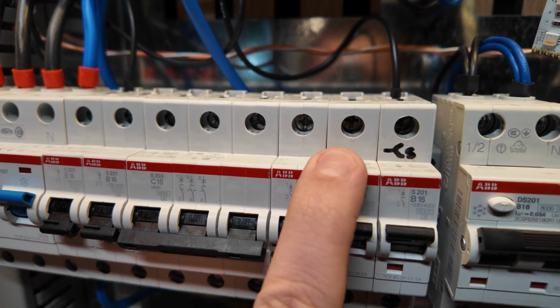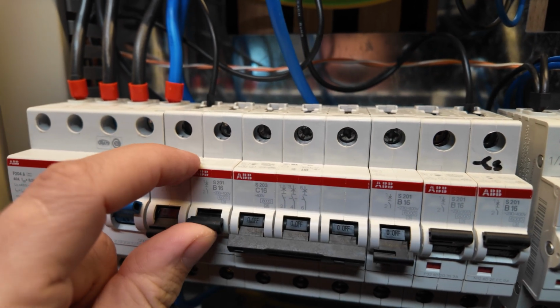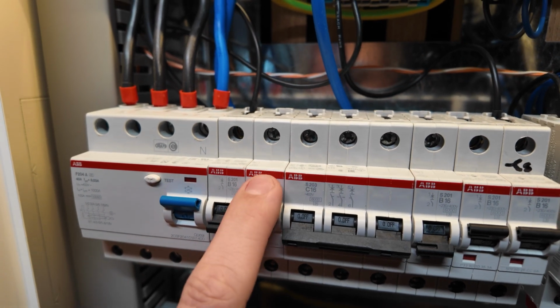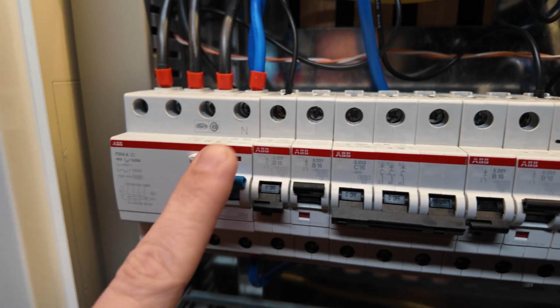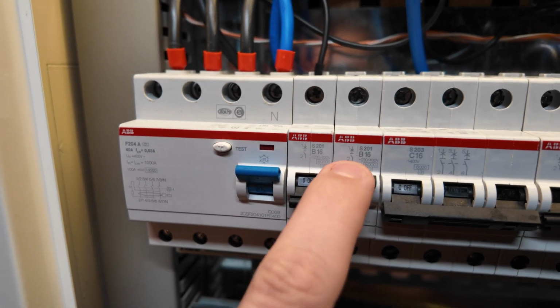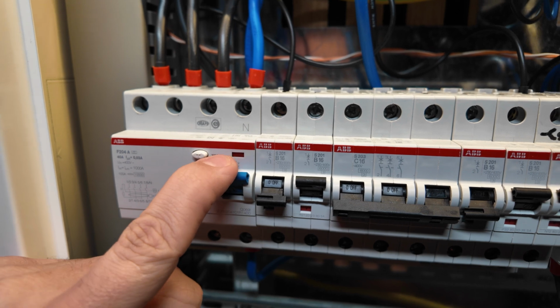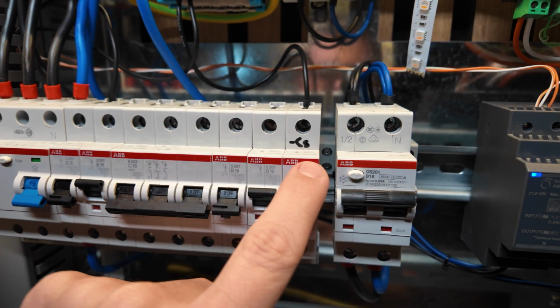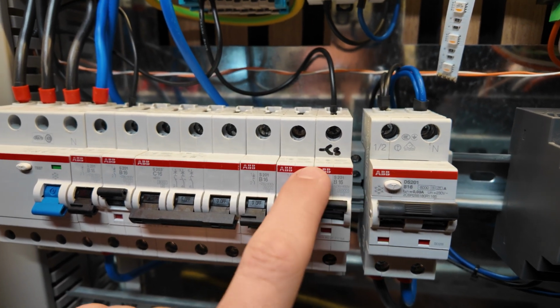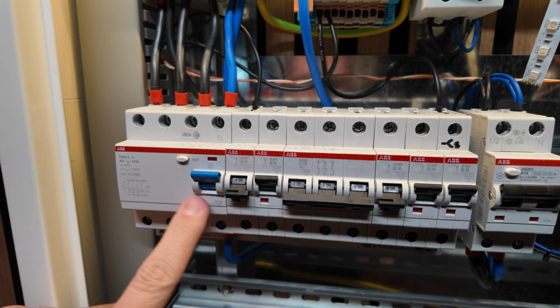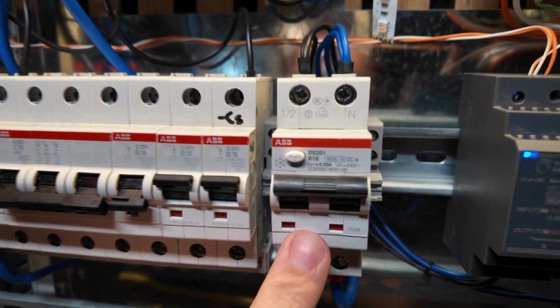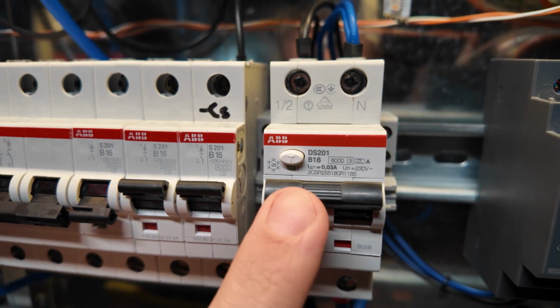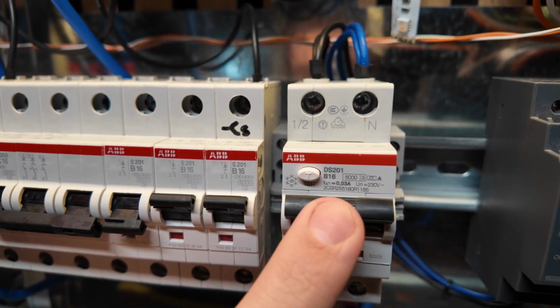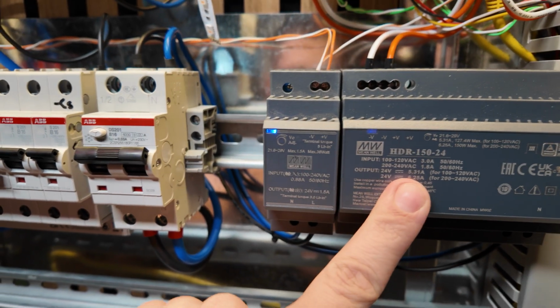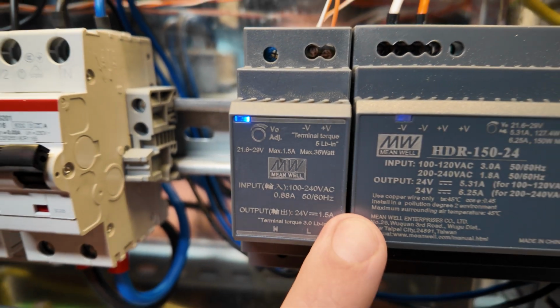But one major issue I see here is, let's say this one is the kitchen, and maybe in the kitchen there is a fault which triggers the RCD and not the breaker. Then for all the breakers connected here, there is no more power, also not for Loxone. To prevent this, I'm using a dedicated one-phase breaker RCD combination, which is then connected to, in this case, two 24-volt power supplies from Meanwell.